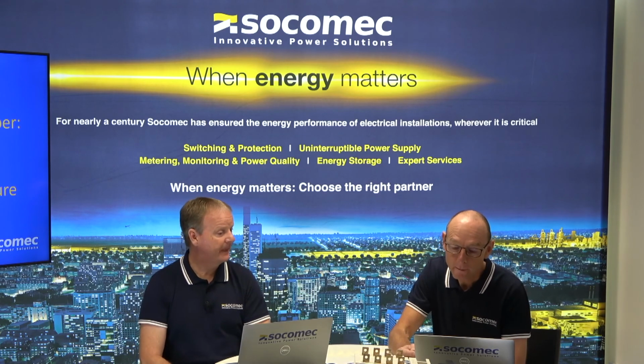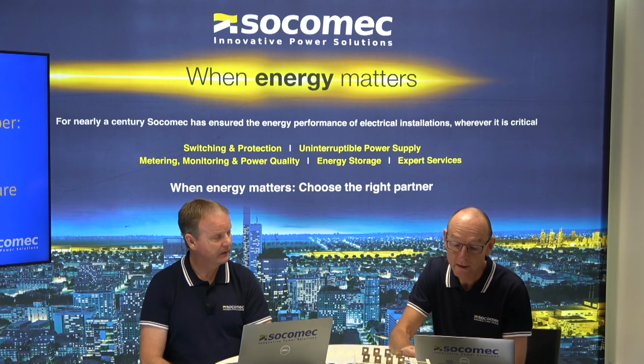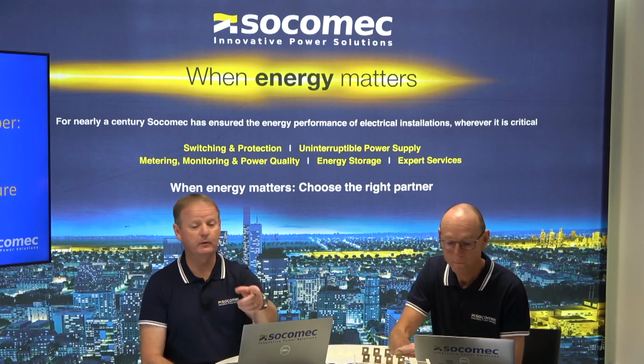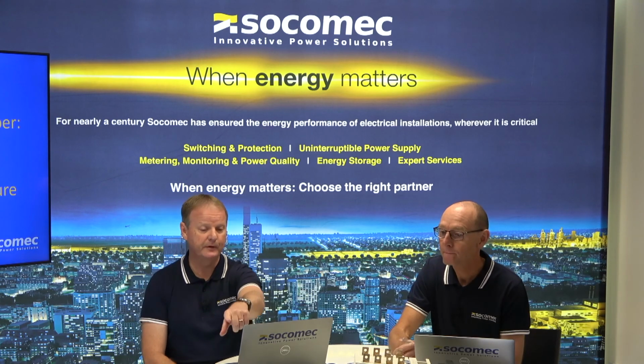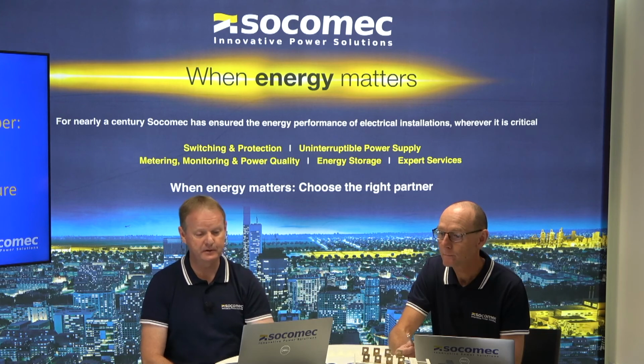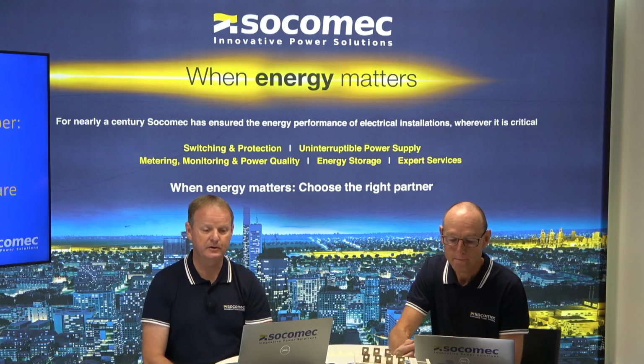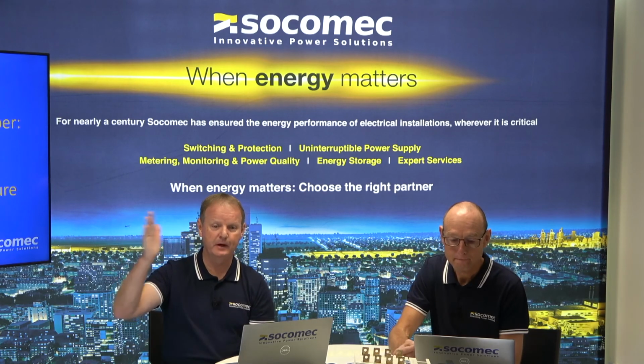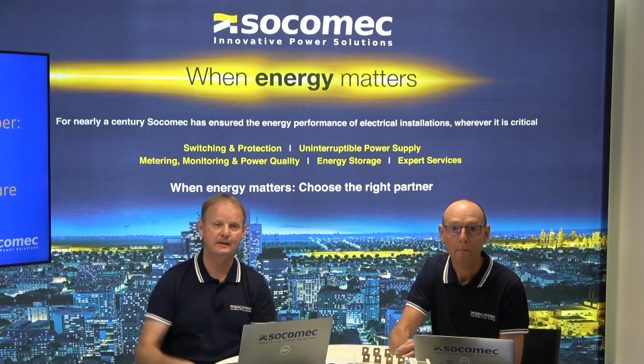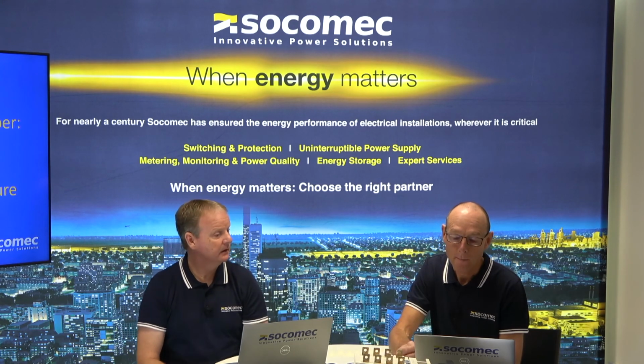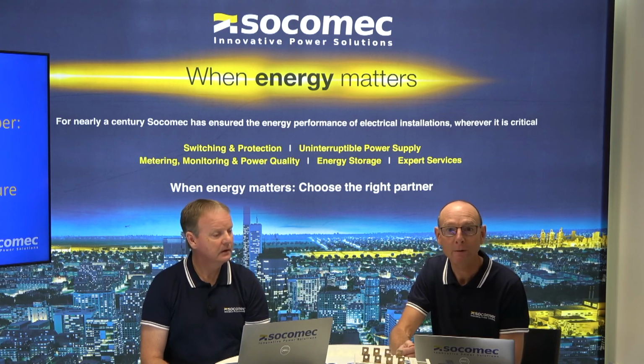Question from Ben. In section 6, figure 1 in the diagram shows multiple signals terminating at a generation set. Does Socomec have a device that accommodates this as a gen start signal in a single point? Yes, so it's a good question too. Both the one I showed you, the ATS-G, which is the one with the dip switches, or the ATS-P, have an automatic gen start signal, which automatically, once it sees the loss of the frequency going down on source 1, will send a start signal to the generator to start the generator. And Ben, if you need some more information on that, please come to us.